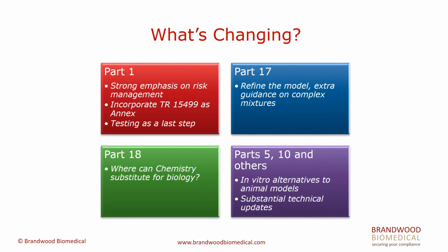What's actually changing? Part 1 will incorporate that risk management annex and continue to emphasize the role of risk management in evaluation. Part 17 is undergoing a major revision where the model for determining allowable limits of leachables will be refined, and doing things like adding extra guidance on complex mixtures.